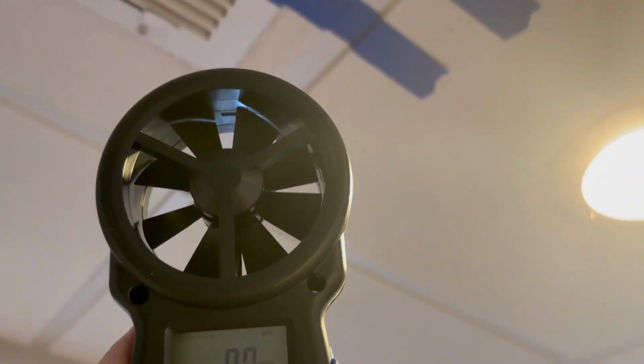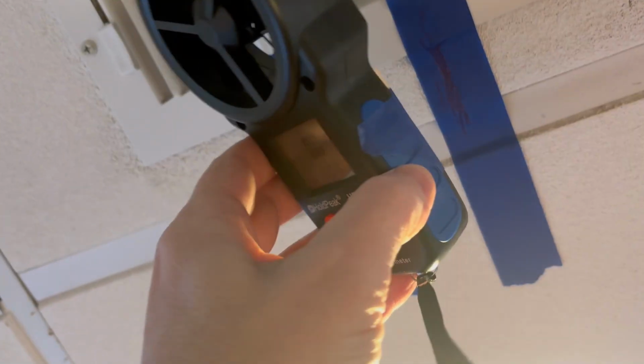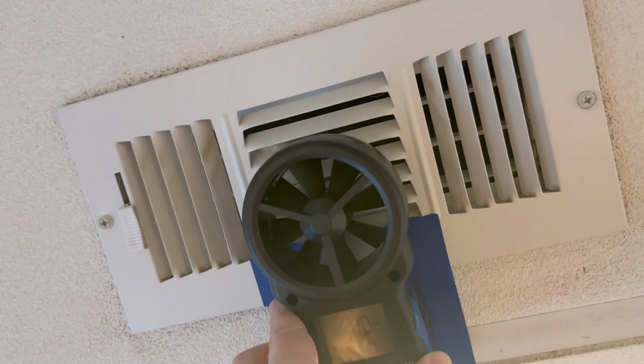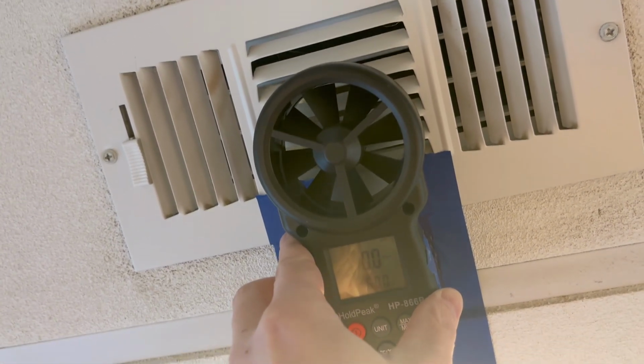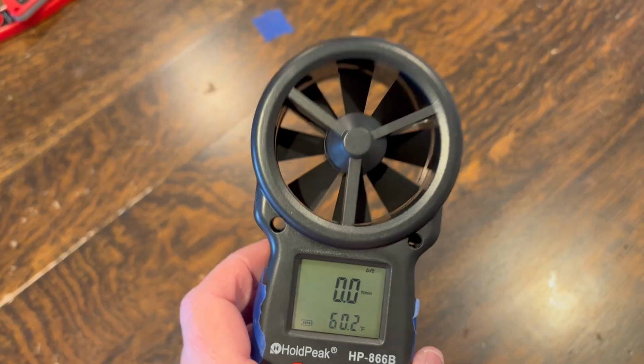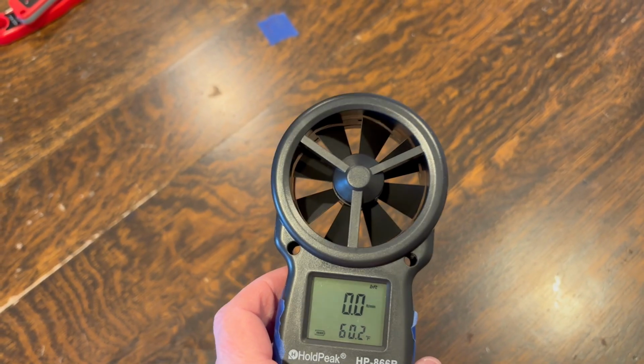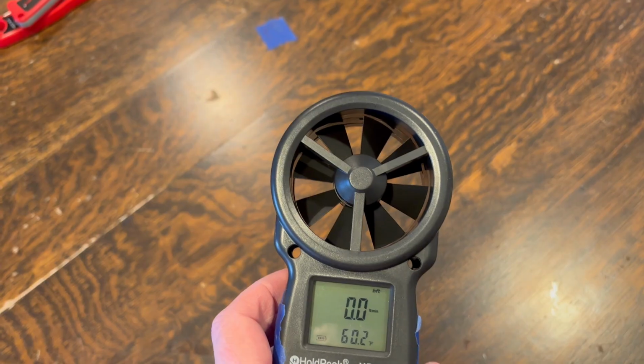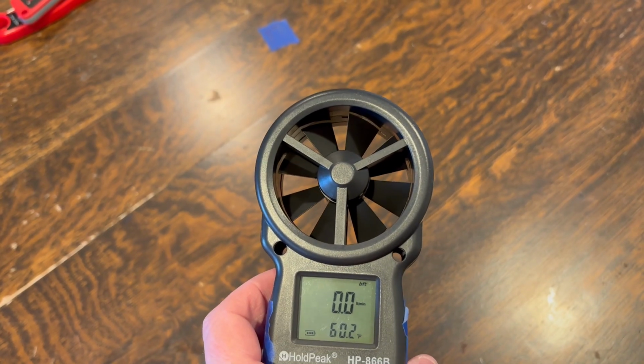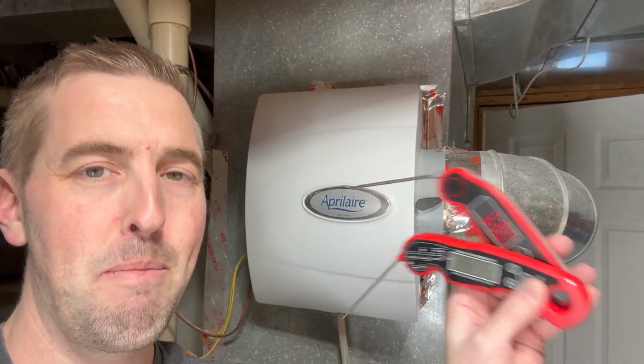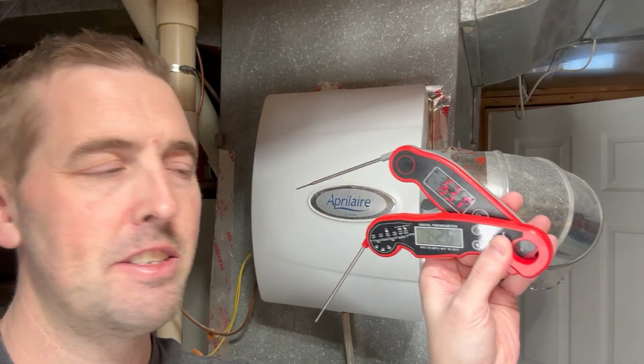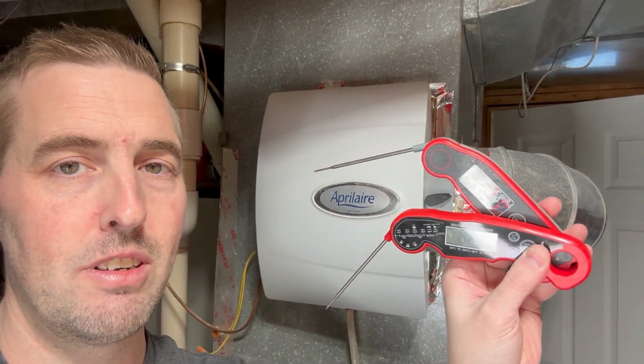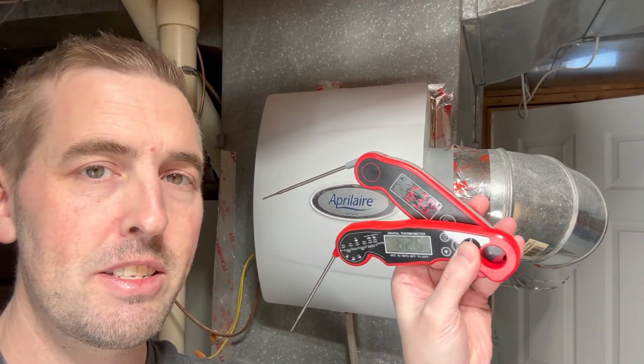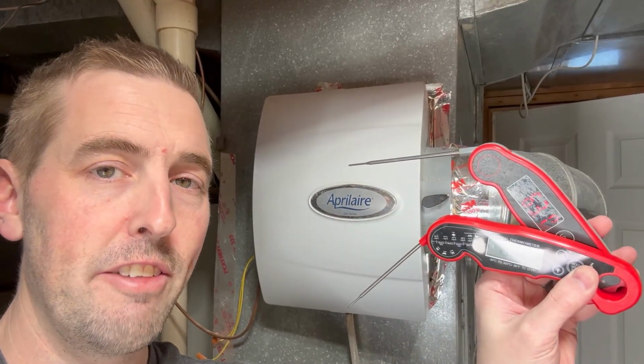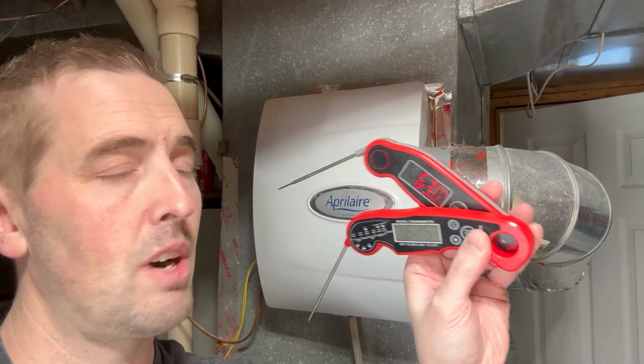And to use our anemometer, we will be positioning it up against a supply register. And what will happen is when the furnace is on and air is blowing through, it's going to spin around. The faster the speed, that means the more air that we're moving through and the less restriction we have at the furnace. And then lastly, we're going to be measuring temperature using our meat thermometers. These are going to be positioned at the supply and return side of our furnace, allowing us to calculate the temperature difference or the delta across the furnace.